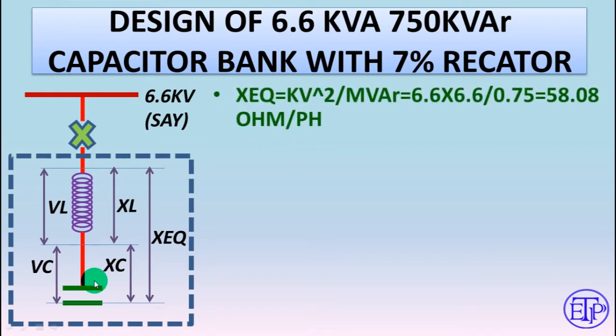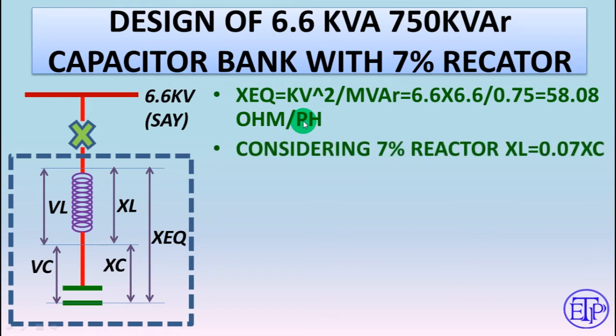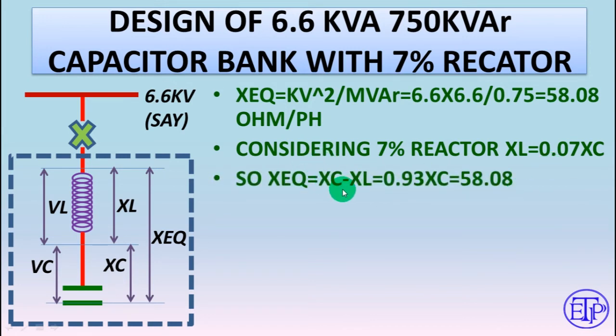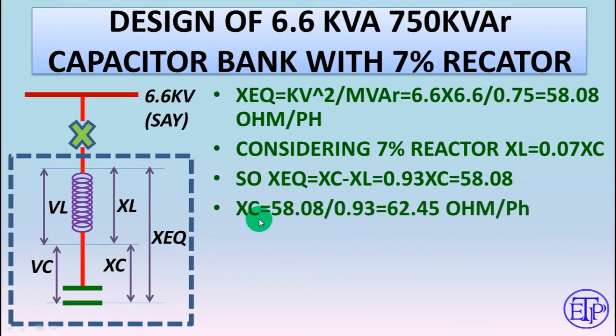XEQ equals kV² / MVAR. We know that impedance equals kV² / MVA, so from that we can calculate XEQ = 58.08 ohms per phase. We are designing with a 7% reactor, so XL equals 7% of XC. X equivalent equals XC minus XL, giving 0.93 × XC = 58.08, which means XC = 62.45 ohms per phase.